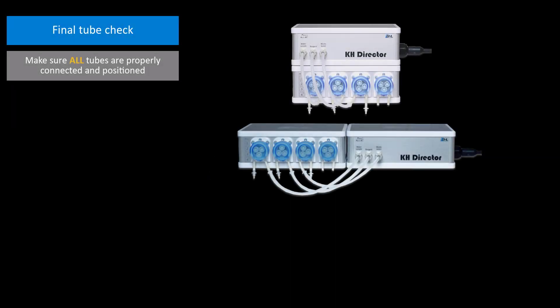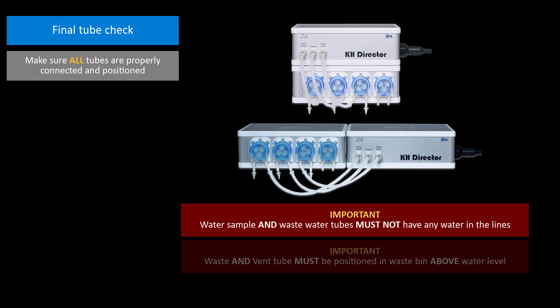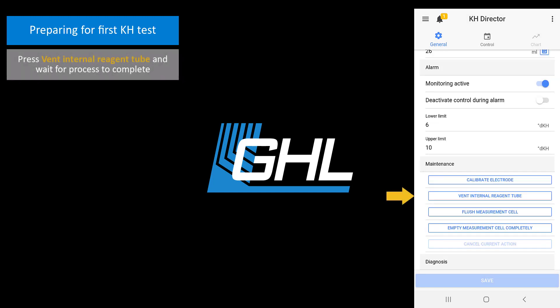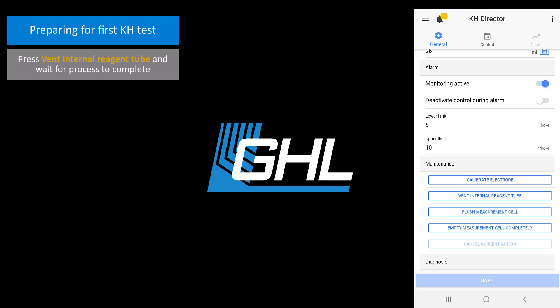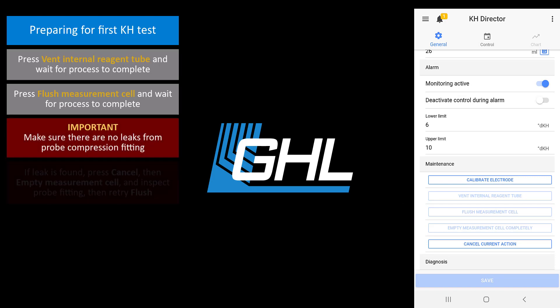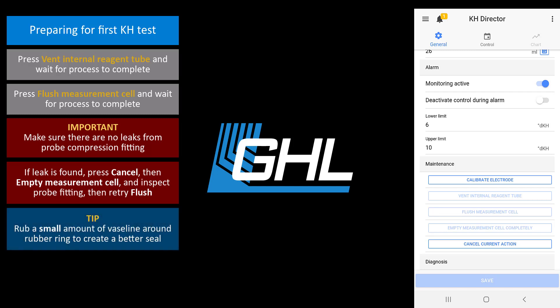At this time, make sure all your tubes are properly positioned and connected. Make sure the water sample tube does not have any water in it, and is already placed in the area where you want to pull the water sample from. The wastewater and vent tube should also be empty and positioned above the wastewater bin. We can now prepare the KH Director for its first test. Press the button that says Vent Internal Reagent Tube. The reagent head will now turn on and prime the reagent tube inside the KHD. When that part is done, press the Flush Measurement Cell button. Check for any leaks around the probe compression fitting. If you see any leaks or drips, press the Cancel Current Action button, then press Empty Measurement Cell completely. Check your probe compression fitting and retighten it. You can also put some Vaseline around the rubber ring to create a better seal. Once that's done, retry the Flush Measurement Cell step.